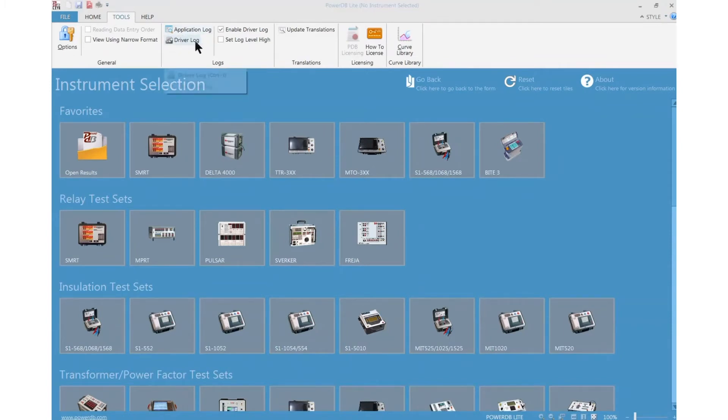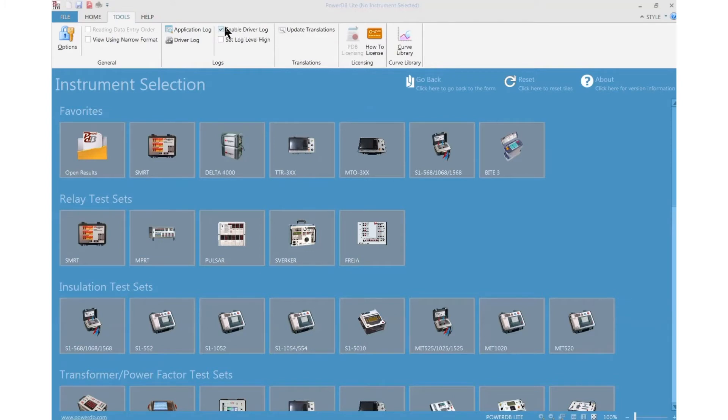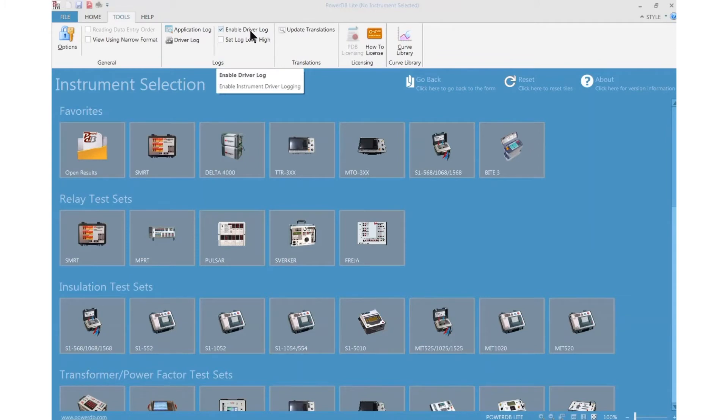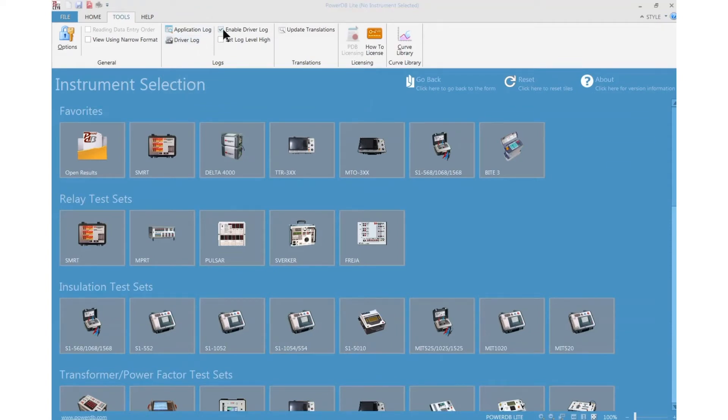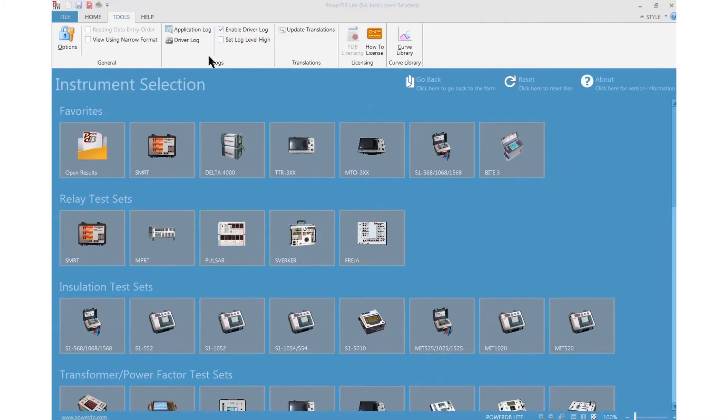This driver log will be active if this checkbox is selected, enable driver log. By default the software should have these, but if there's no checkbox here then we won't have any driver logs there. So in that case you will need to check it, run one more test for the instrument to generate the driver logs, and be able to get those.